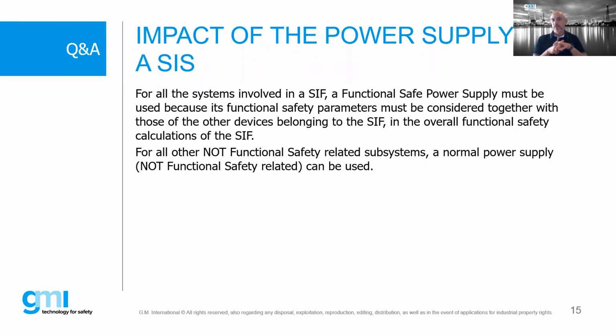It's very important because the functional safety parameters must be considered together with the functional safety parameters of the other devices in the SIF. So it's very important that you obtain them from your power supply's manufacturer and make a calculation with all details. Of course, for all the other systems not related to functional safety, normal power supplies without safety parameters can be used.